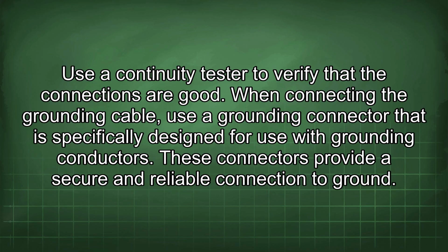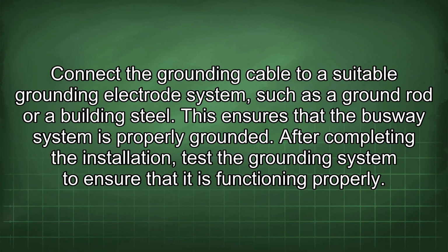When connecting the grounding cable, use a grounding connector that is specifically designed for use with grounding conductors. These connectors provide a secure and reliable connection to ground. Connect the grounding cable to a suitable grounding electrode system, such as a ground rod or building steel. This ensures that the busway system is properly grounded.